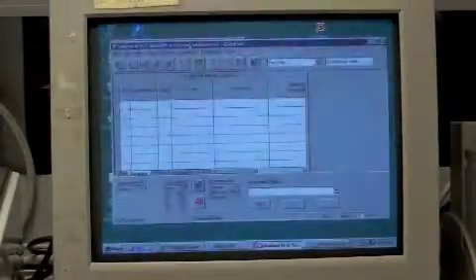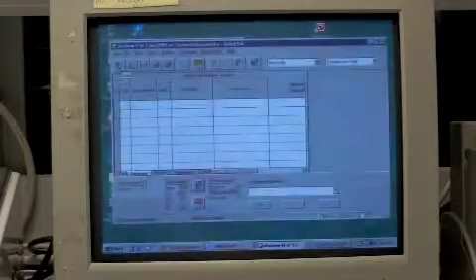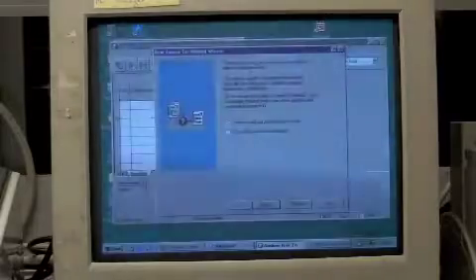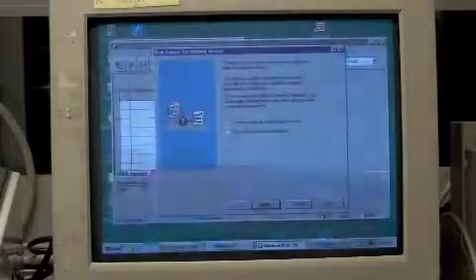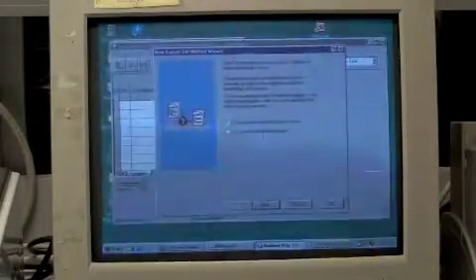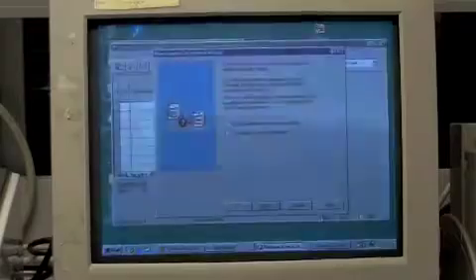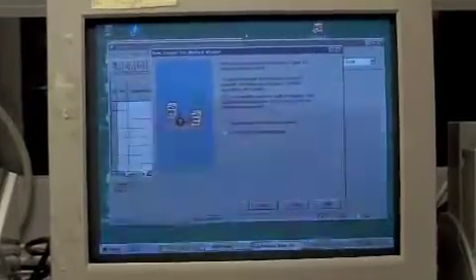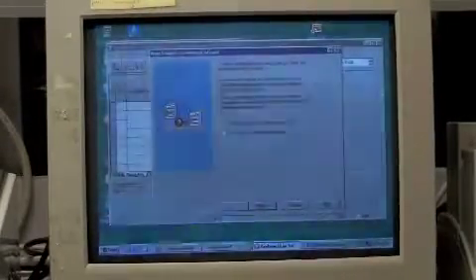If this is your first time using this software, the button you're going to be pressing is this one here. If you have a look, it's called the Software Wizard. This is a lengthy process whereby you can build an entire HPLC method from scratch — which is exactly what we're going to do: create a sample set method from scratch.